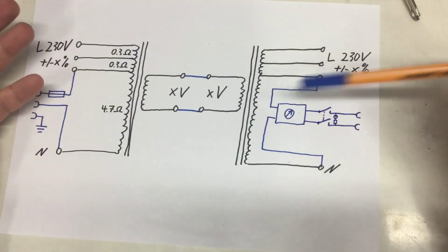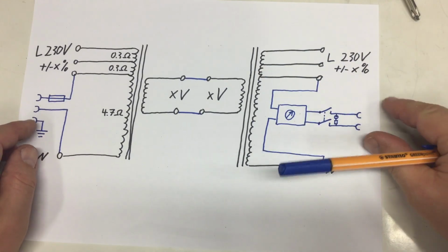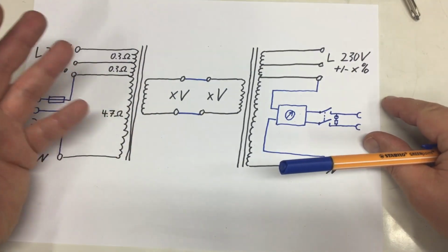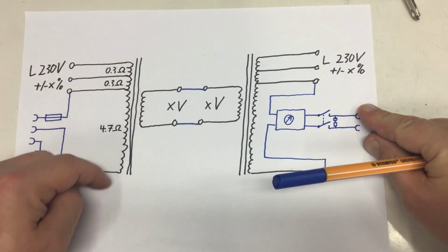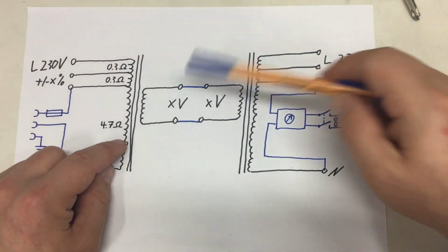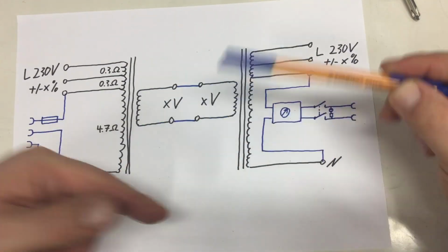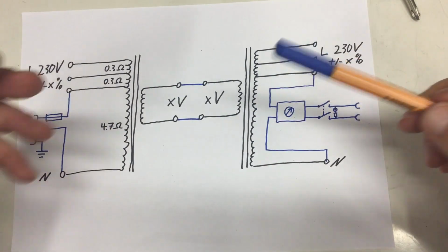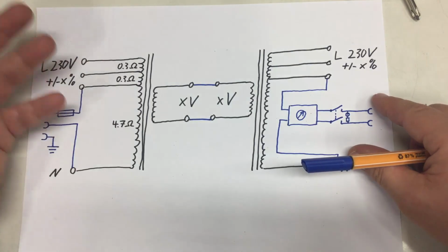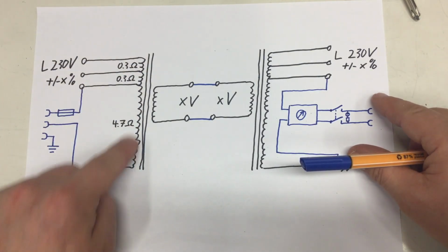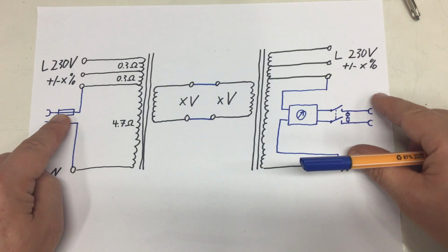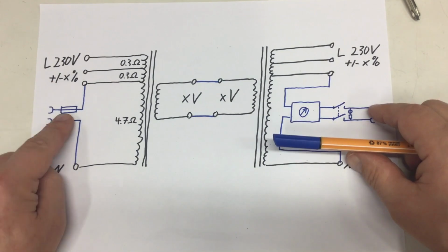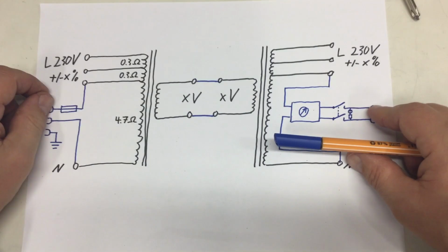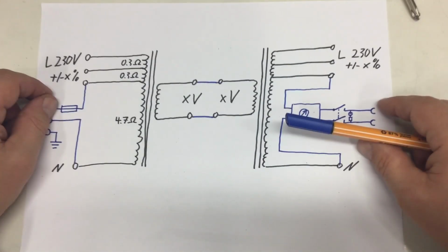You could add another fuse in that circuit here, but this is, how shall I put it, the highest energy coil, okay? Because with each transformer core, we got some thermal losses. So the most electrical power that we expect will be in that coil. And so if we fuse that coil, if we have an overload here, that fuse should save the day. Hopefully. We'll see.